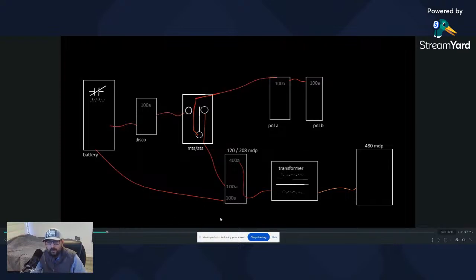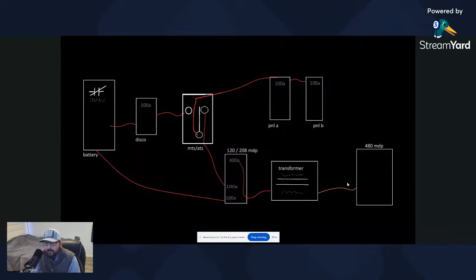So this is the normal flow of this. We've got the 480 that feeds this transformer, 480 volts. I don't know what the size breaker was here. We went into the transformer and we came out to a 400 amp breaker as we should. The problem was with this guy actually ran 500 and not 600. So as we know, what we just discussed was that 500 is only good for 380 amps. So this was actually no good.